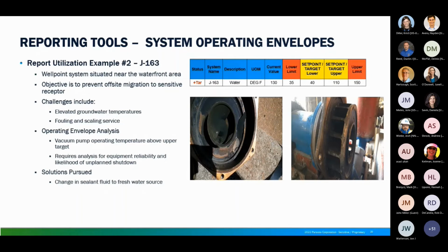The next example is for one of our well point systems, J163. This particular well point system is located near a waterfront area on the processing facility. Again, you can see the cutaway of the operating envelope on top. There are two graphics showing the liquid ring vacuum pump focus here. This particular system's objective is to prevent offsite migration to a sensitive receptor. The challenges for this particular system are that we have elevated groundwater temperatures in the area, for different reasons than we see on the rest of the site. But because of those elevated groundwater temperatures, we see a lot of fouling and scaling.